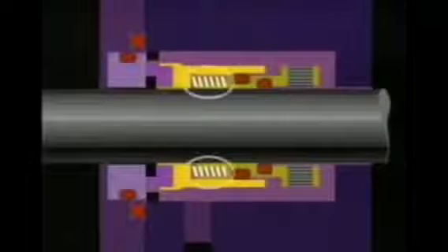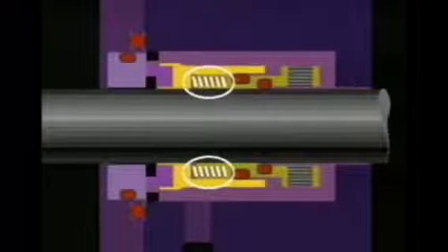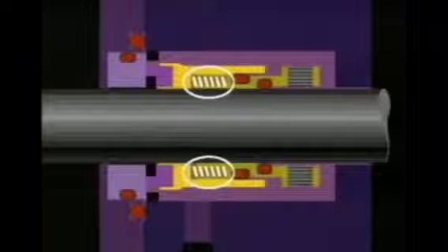Next, spring pressure is incorporated to help hold the faces together. The spring pressure also serves to compensate for end play and some shaft run out.